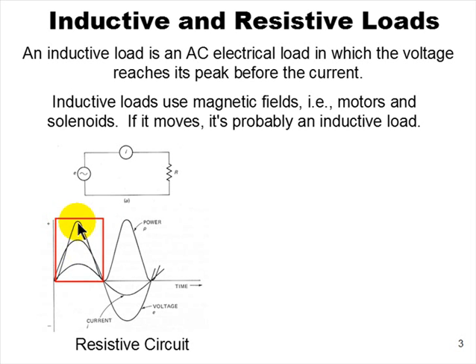It's always higher. So this is your power. That's your watts, voltage, and amperage. They all peak at the same time. Resistive load, you turn the toaster on. This is what you get. Voltage, amperage, VA, they all peak together. The toast is done. It pops out. They all go to zero. Current flow doesn't matter whether it's alternating or direct.